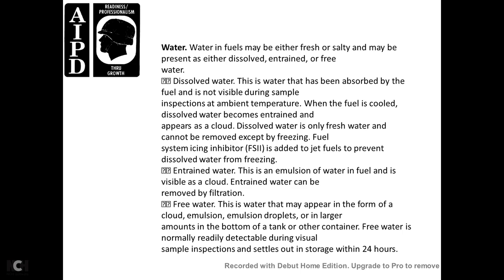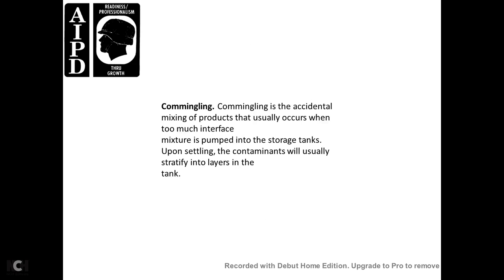Dissolved water is always fresh water and cannot be removed except by freezing. Fuel System Icing Inhibitor (FSII) is added to jet fuel to prevent dissolved water from freezing. Entrained water is visible as a cloud in the fuel and can be removed by filtration. Free water may appear as a cloud, emulsion droplets, or as a larger amount at the bottom of a tank. Free water is readily detectable by visual sample inspection and settles out in storage within 24 hours.